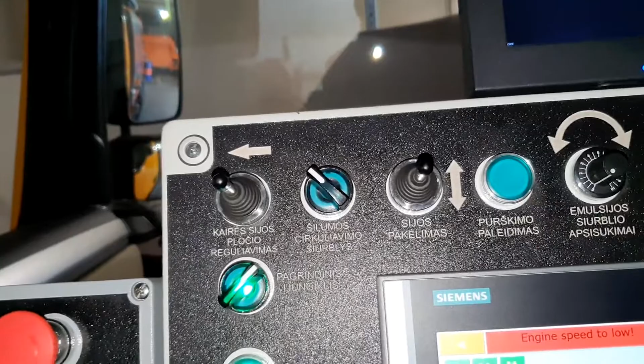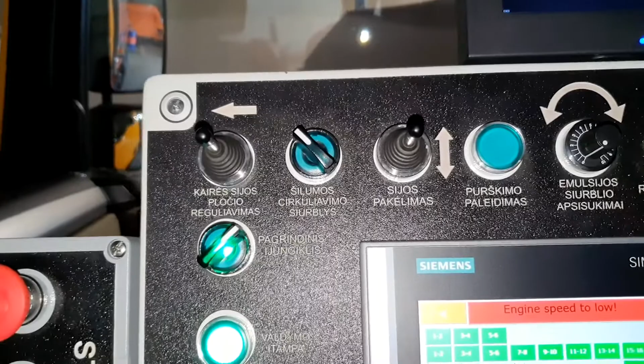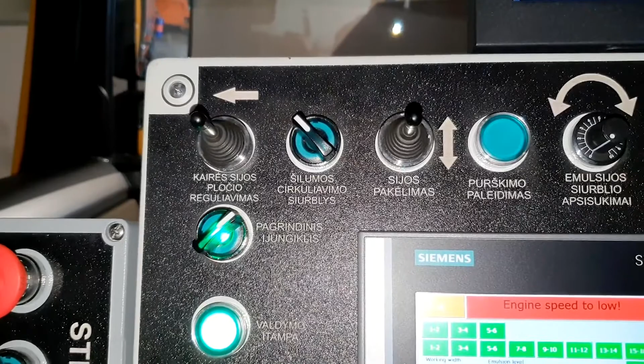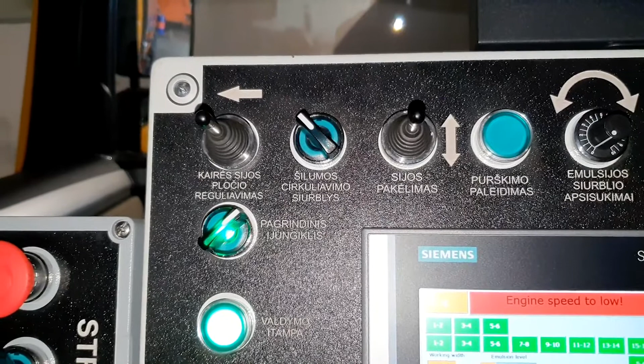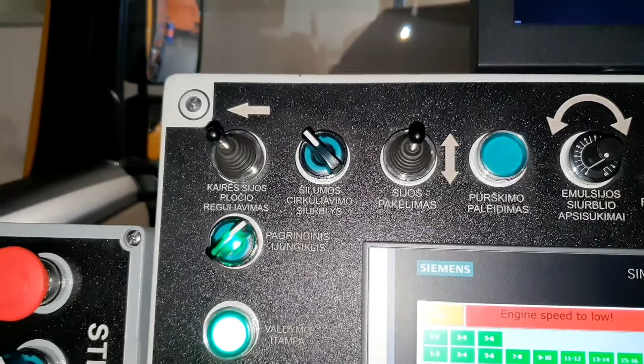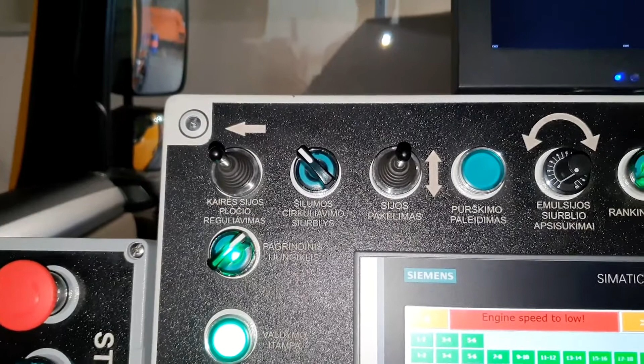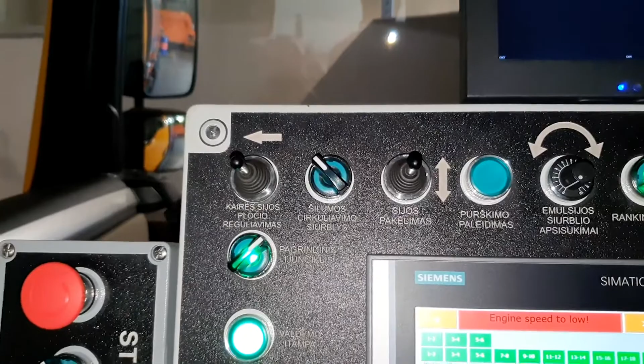The next switch here is responsible for our internal circulation system with the heat exchanger, where we heat up the emulsion pump and the emulsion filter. As I mentioned before, we use heat from the Kubota engine, exchanged by a plate heat exchanger, and then pumped through the coat of the pump and filter. This way, startup is much easier every day, and we prevent the pump from being clogged and stopped.